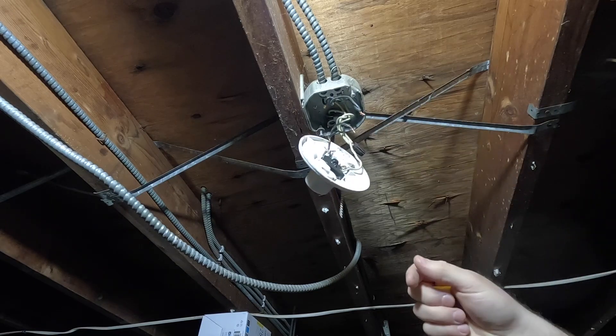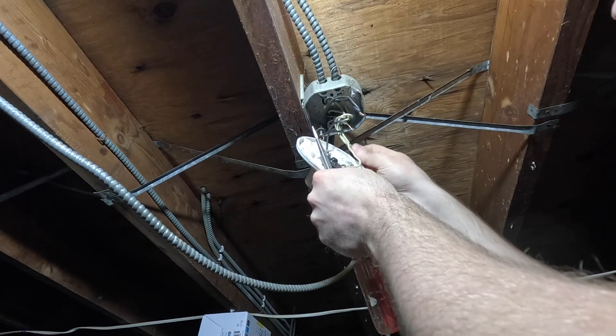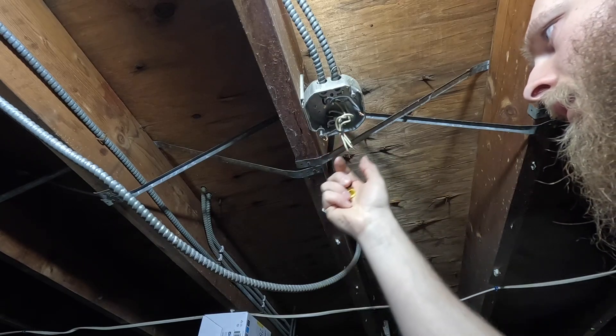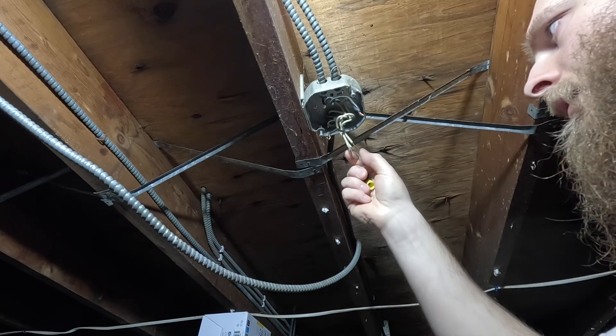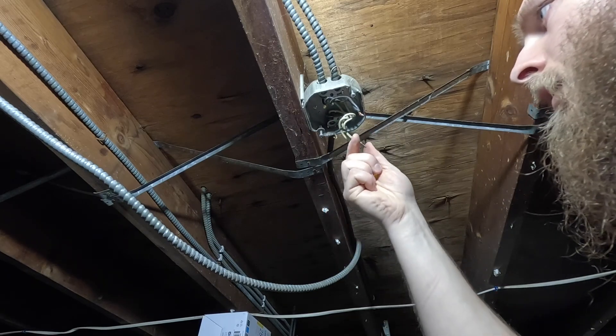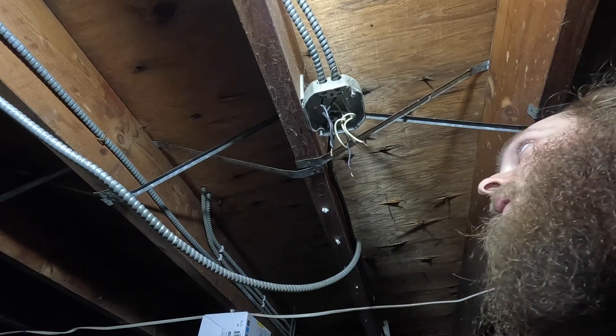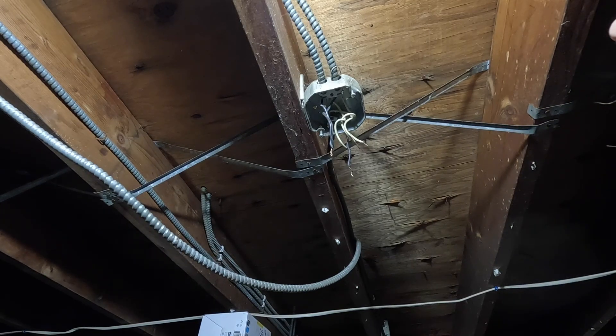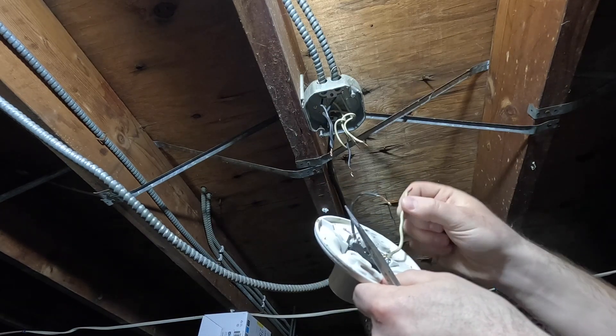These two are connected properly and then the rest just is not. This wire all looks relatively okay — I'm checking for that liquidy stuff that shows up when the insulation degrades. I'm not really seeing any of it on there, not on the high side either, so these pieces look okay for now. They are all going to get redone eventually. I think what I'm going to do is when I put the new fixture in — oh wow, look at this.